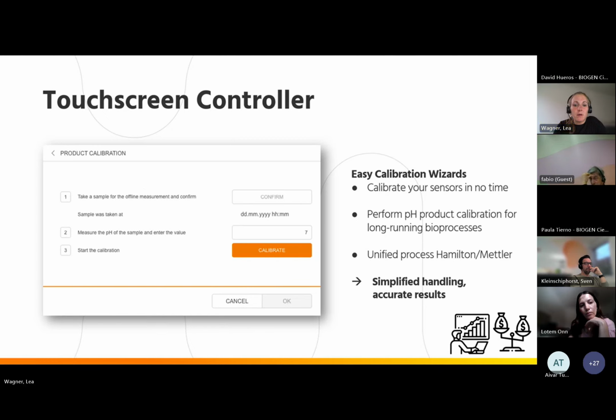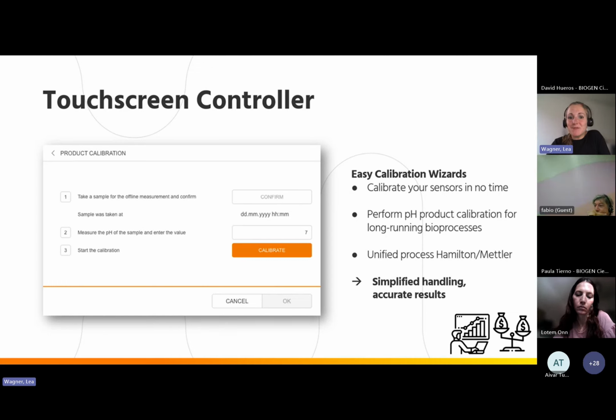And it's also the same no matter if the customer has Hamilton or Mettler sensors, and for long running processes the customer can also do a pH product calibration. So this calibration wizard simplifies the handling, and the customer gets more accurate results, because if something goes wrong during calibration, the results of the bioprocess are at the end basically worthless, because the sensor measures not the right value. So the calibration step is very important, and we made it as easy as possible, with a very low or no risk for the customer of doing something wrong.